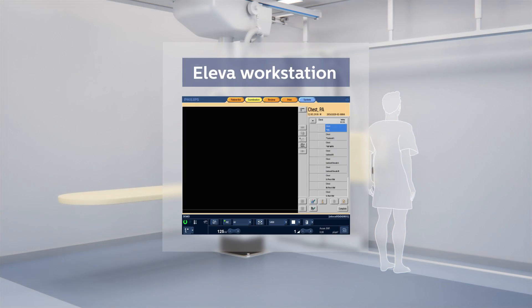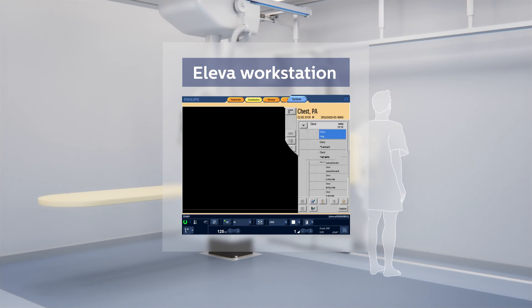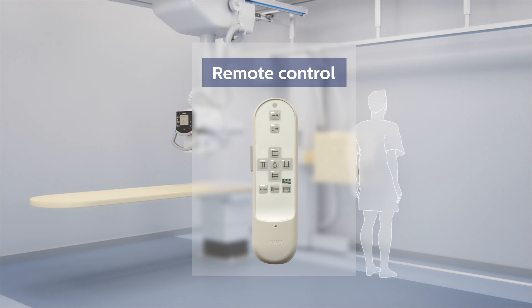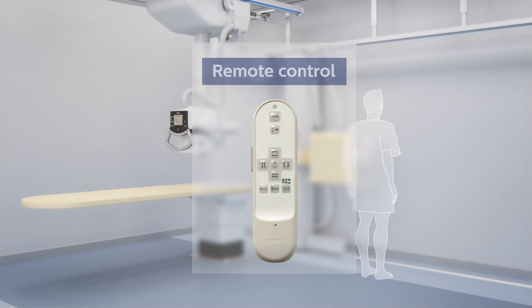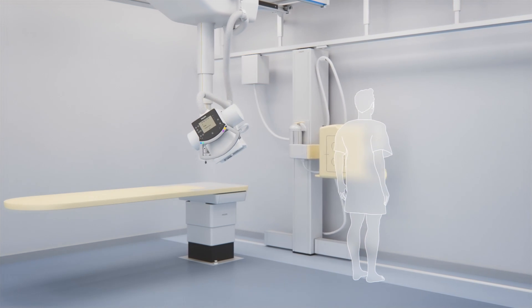Comfort Position allows for all of the motorizations included in ComfortTrack and ComfortMove, while also allowing for simultaneous movements of the ceiling suspension and detector.